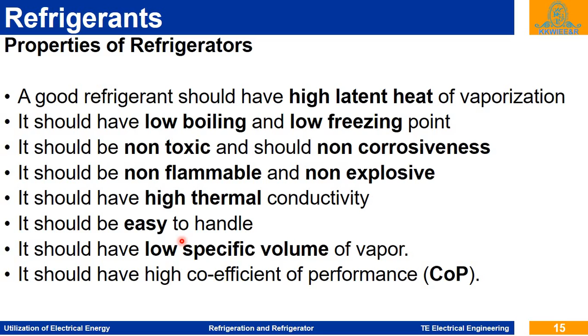A low boiling point and low freezing point are needed because they work at minimum temperature, so the refrigerant must absorb the heat from the cold medium. That's why it must have a low boiling point, so it absorbs heat from the area to be cooled. When there is a leakage of these refrigerants, they must be non-toxic for the environment as well as human health. It should be non-corrosive when passing through the metallic tube. In case of leakage, it must be non-flammable or non-explosive. Then high thermal conductivity: when it passes through the metal tube it absorbs heat, and this heat is carried out in the condenser, so it must have high thermal conductivity and be easy to handle. So these properties must be had by the refrigerants.